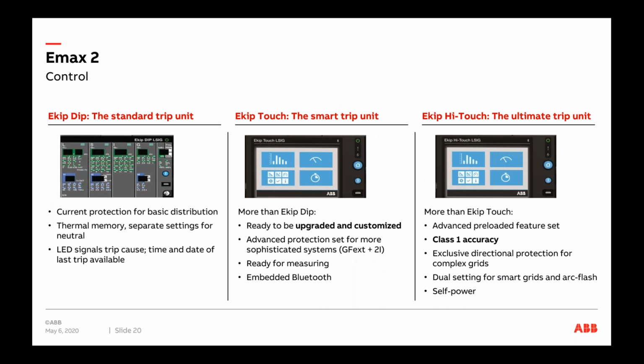Now, speaking of the trip unit, we only look at three kinds. We have the Ekip Dip, the Ekip Touch, and the Ekip Hi-Touch. The Ekip Dip is a straightforward trip unit, quite basic in nature in terms of its capability. And in terms of its advanced capability, it still allows us to have the complete range of protection. However, if you're looking at logic or embedded logics within the breaker or higher levels of certain protection, for example, if you're looking at having two kinds of ground fault on that certain breaker, would be a standard ground fault protecting the ground and a secondary ground fault, which let's say call it, let's talk about restricted earth fault. So if you want REF protection, that may not be possible in the dip, which allows us to have that functionality with the Ekip Hi-Touch and to an extent even with Ekip Touch.